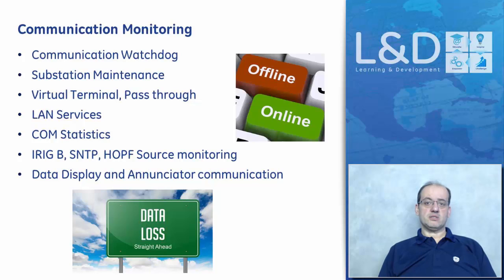You might have annunciators in your substation. So when the dispatcher sends an engineer to the site, he comes and he can locate the issue without connecting his laptop to a device in order to find out what the alarms are. This annunciator would be like a panel with little illuminating windows that would turn on in order to indicate a certain alarm that will assist the field personnel in immediately locating the alarm in the substation and going directly to the point of failure or the point of the alarm and trying to service it much faster.